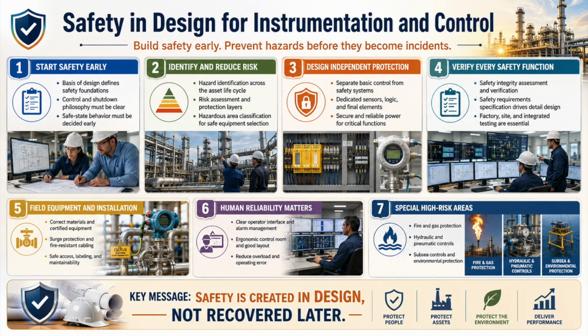For every required safety function, define the initiating condition, trip point, required risk reduction, response time, final safe state, reset philosophy, alarm behavior, bypass controls, maintenance overrides, architectural limits, unwanted trip requirements, and operator interface. These requirements form the safety requirement specification. Without this specification, detailed design has no stable safety target.